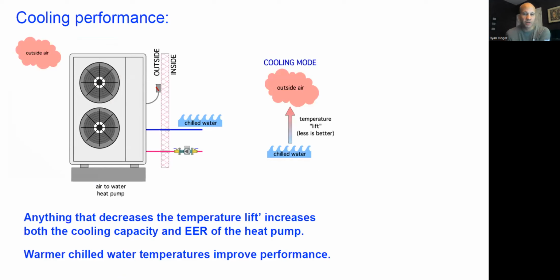So how's this going to work? Similar to the drawing that we had last time for hot water, we have, in this case, an air to water heat pump. Sitting outside, I have to have my air to water chiller, my air to water heat pump. And it's going to have chilled water moving into the building and warmer water coming back. Like I said, historically, we're trying to get 44 and 56. Some jobs might be designed for 45 or 46 or 47. Some jobs may have a bigger than 12-degree spread, but something in that general area.